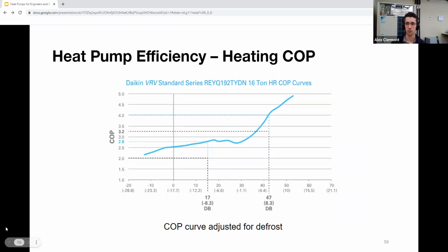So now we want to look at a true application for a true machine. And this is a 16-ton heat recovery. And what we're looking at here is actually a COP curve for that machine. So moving from right to left, we see that the temperature goes down. So it's plotting temperature versus COP of that machine. So as we move from the 50s, we're at about a 4.5 COP. As we go down to 47, which is a published AHRI point, we have a COP of 4. As we keep going down into the 30s, we have COPs right around 3 and 2.8, and actually at 17, the COP is 2.8.